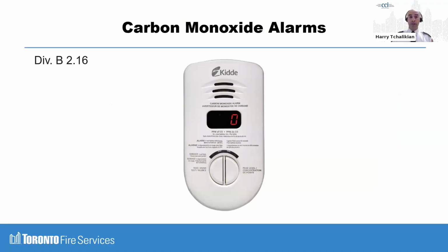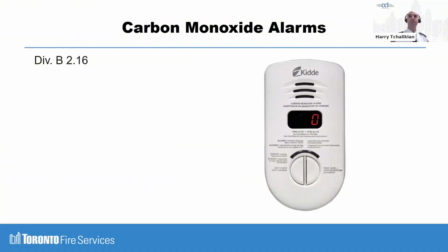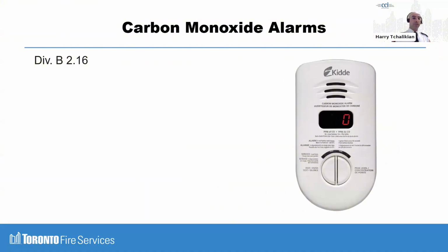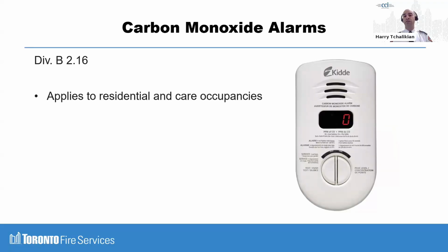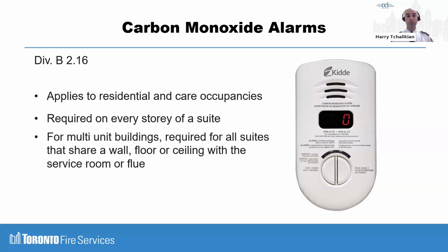Next, we get into carbon monoxide alarms. So Division B 2.16 applies to residential and care occupancies. The new addition here is care occupancy. So B3, is this a care facility? That's new. Required on every story of a suite, where previously it was only required on the story that had the sleeping room. And for multi-unit buildings, required for all suites that share a wall, floor, or ceiling with the service room or flue. The new addition here is the word flue. That's new in the new fire code.